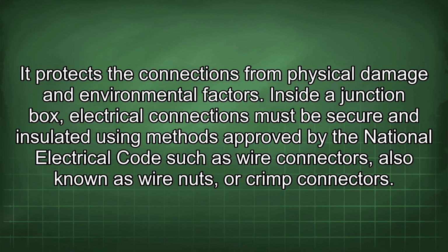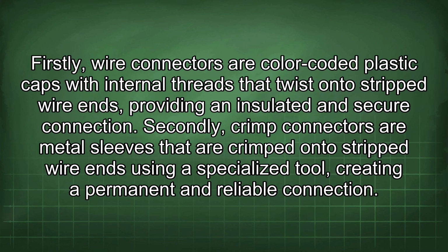Inside a junction box, electrical connections must be secure and insulated using methods approved by the National Electrical Code, such as wire connectors, also known as wire nuts, or crimp connectors. Firstly, wire connectors are color-coded plastic caps with internal threads that twist onto stripped wire ends, providing an insulated and secure connection. Secondly, crimp connectors are metal sleeves that are crimped onto stripped wire ends using a specialized tool, creating a permanent and reliable connection.